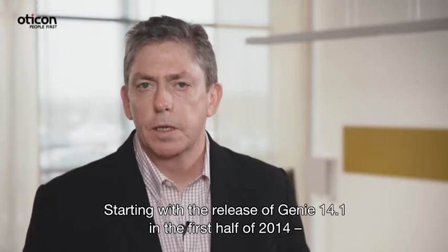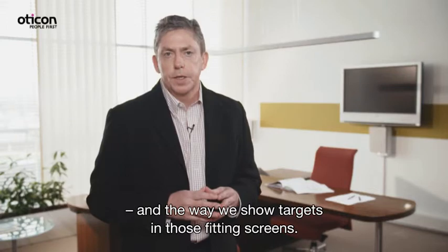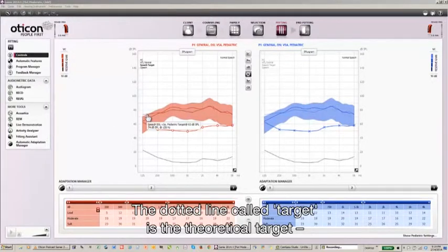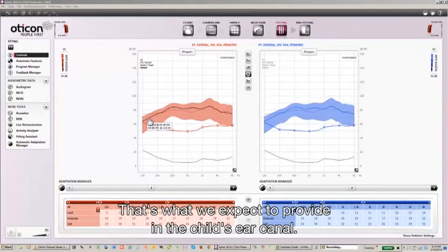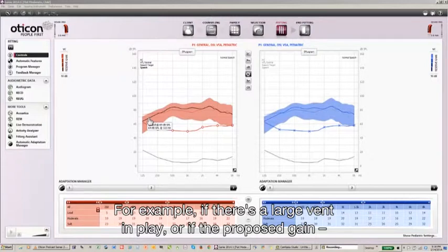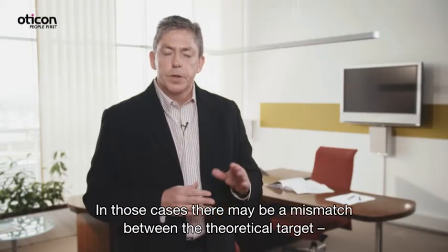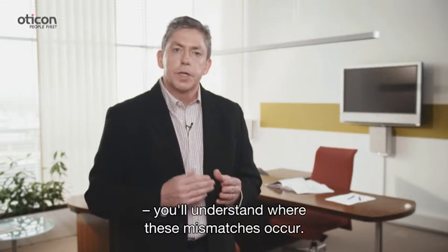Starting with the release of Genie 14.1 in the first half of 2014, we're changing the way we show screens in Genie and the way we show targets in those fitting screens. When you open a Genie fitting screen, you'll now see two different lines on the graph. The dotted line, called 'target,' is the theoretical target as called for by DSL. The solid line, called 'simulation,' is what we expect to provide in the child's ear canal. The simulation is based on our attempt to meet the DSL targets, but with any corrections necessary for acoustic reasons — for example, if there's a large vent, or if proposed high-frequency gain is at particularly high levels. That way, when you see the same response in your real ear machine, you'll understand where these mismatches occur.